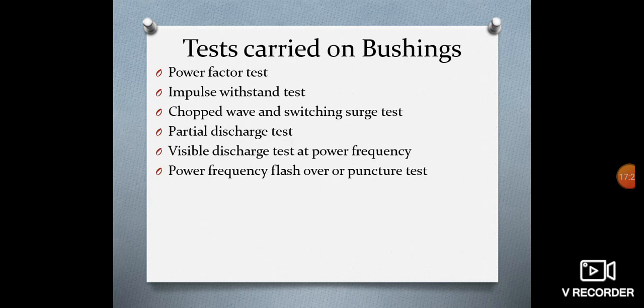The tests carried out on bushings are the power factor test, in which the bushing is installed as in service or immersed in oil. The high voltage terminal of the bushing is connected to the high voltage terminal of the Schering bridge, and the tank or earth portion of the bushing is connected to the detector of the bridge. The capacitance and the power factor of the bushing are measured at different voltages as specified in the relevant specifications, and they should be within the range specified.